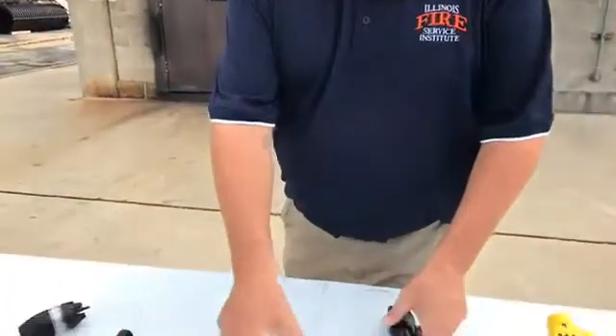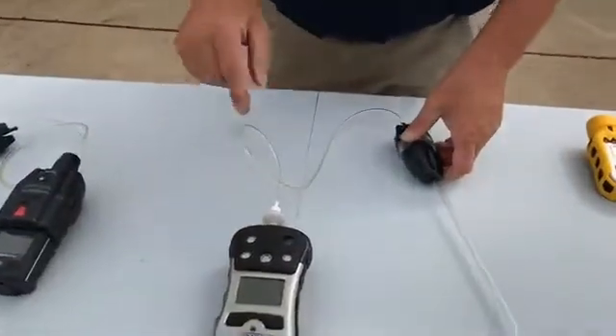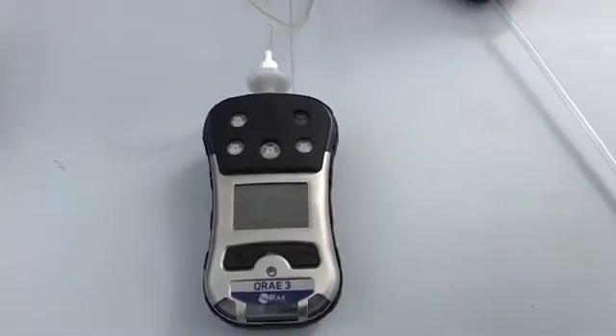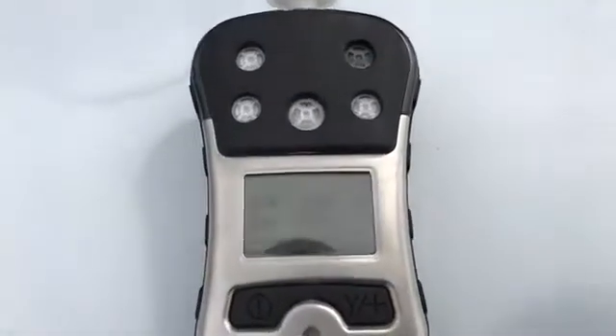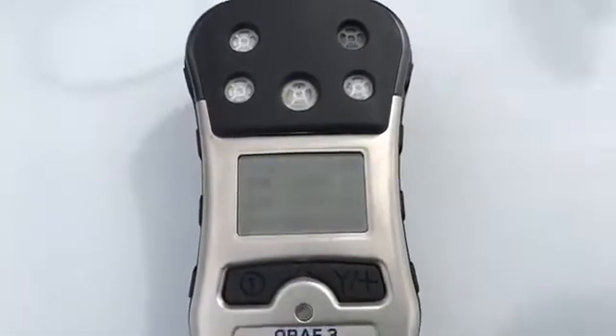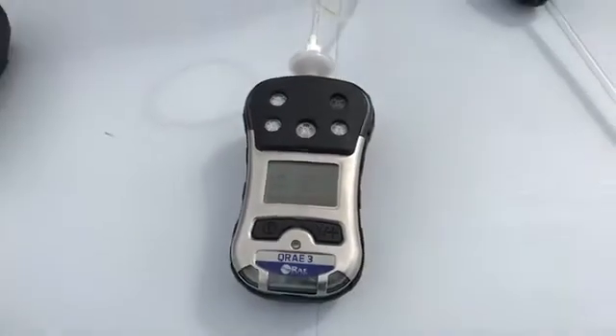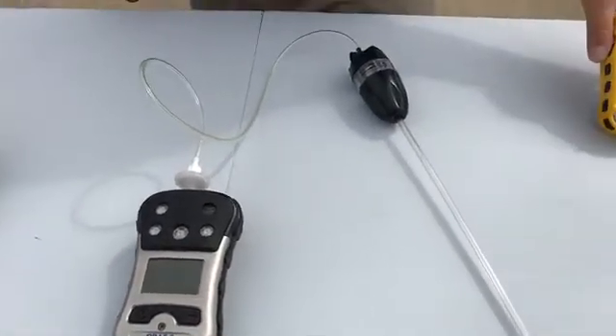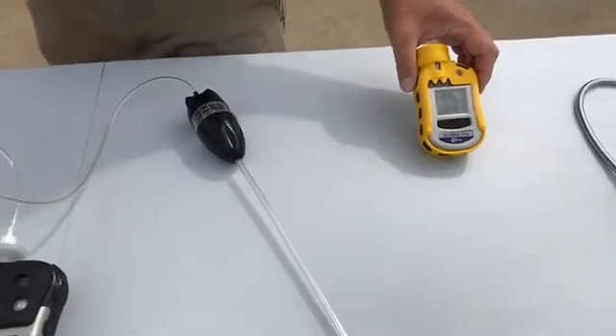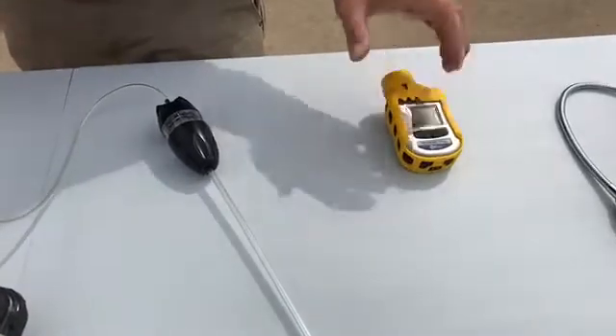Moving on to our next instrument. This now is a 4-gas pumped instrument. You can see the inlet up here, as well as you can probably hear the pump very faintly, but that's how we know it is a pumped instrument versus a diffusion. This single gas has no pump built on it. That would be an example of a diffusion monitor versus pumped.